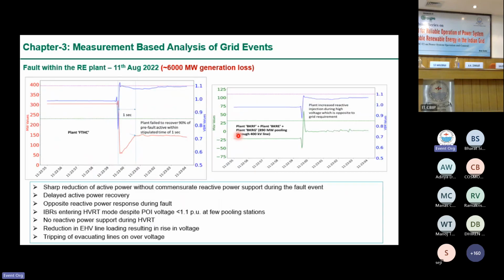For this, we have to go into the performance of specific plants. This is the performance of a specific plant connected at Fatehgarh station. During the fault, the plants are mandated to provide reactive power support in order to arrest the voltage dip. But in case of most of the plants, we did not witness this reactive power support during the fault. Also, the response of some plants was opposite to the desired one. When the plants were expected to inject reactive power, some of them were even absorbing reactive power during the fault.